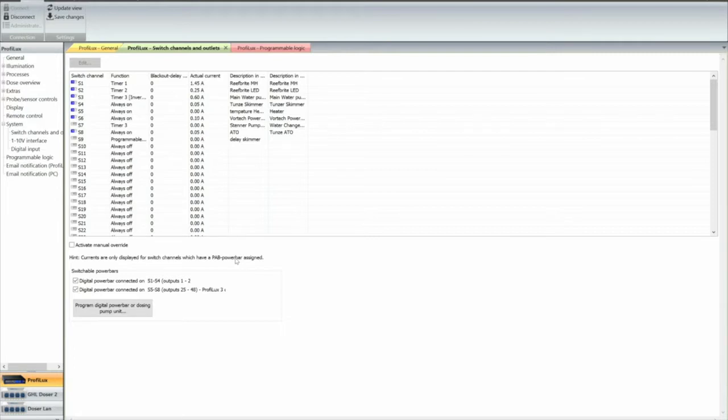And so, then when you hit programming function, the return pump and skimmer will shut off, and after 10 minutes, the feed pulse is over, and my return pump turns back on, and the skimmer doesn't turn back on for another 10 minutes after that.